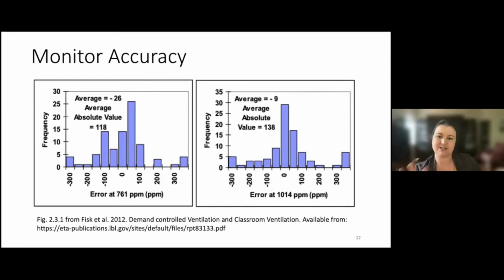In addition to this difference around the two set points, the monitors also varied in terms of what manufacturer made them and the sensor type. There were little differences in design, and whether or not the sensor had a self-calibration feature. Overall, about a quarter of the sensors did not meet California's required 75 ppm allowable error at the upper level. And I think about 40% didn't meet requirements at the lower measurement level. So that's a big problem.